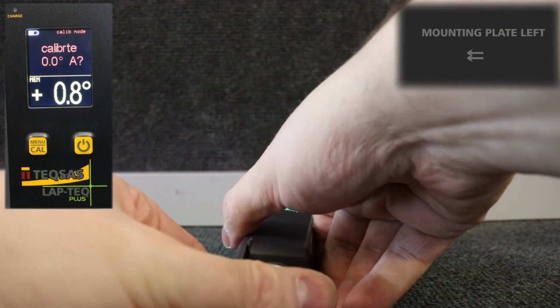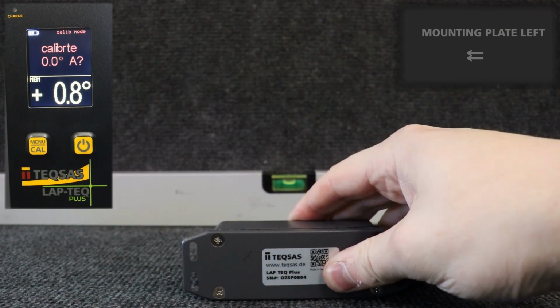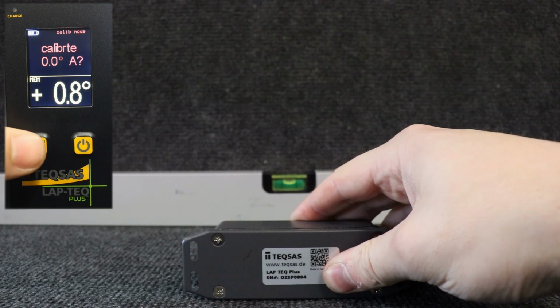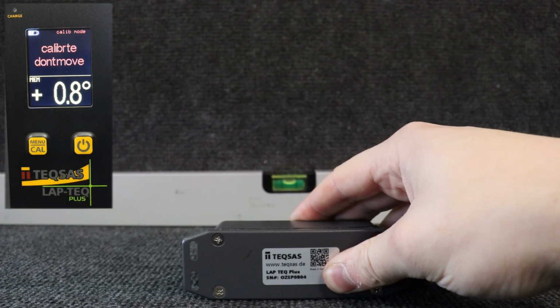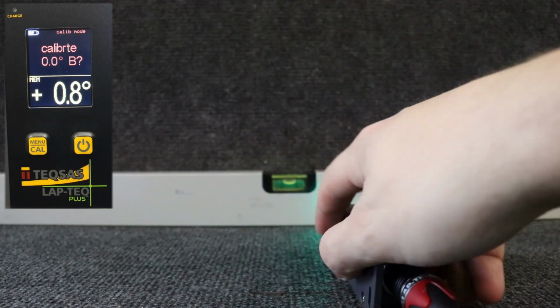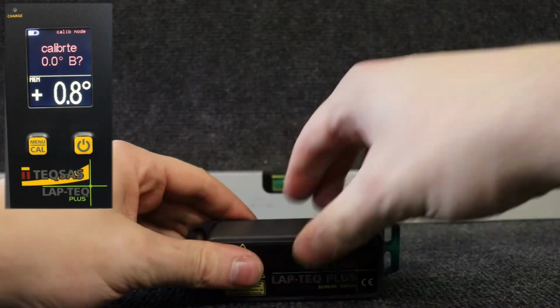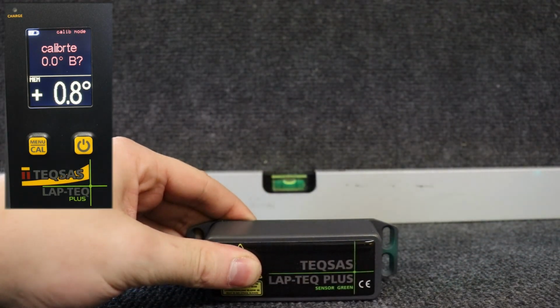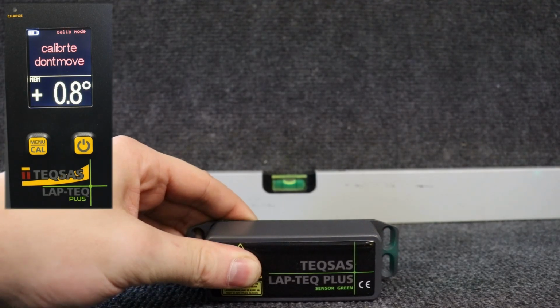This is seen from the side of the XLR connector into the direction of where the laser beam is shooting at. First calibration position is horizontal at 0.0 degrees, the sensor on its side with the mounting plate on the left. For the second position, keep the sensor on the same side, but pointing the opposite direction at 0.0 degrees.